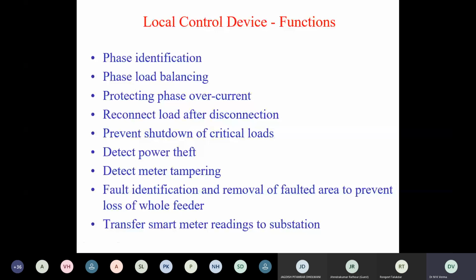The functions of local controllers may be, say, phase identification, meaning which load is connected to which phase, phase load balancing, protecting against overcurrent in different phases, and connection and disconnection of load. If some phase gets overloaded, the local control device should be able to disconnect it. If the overcurrent is reduced and current comes within limit, it can be reconnected. Or if some theft is there.